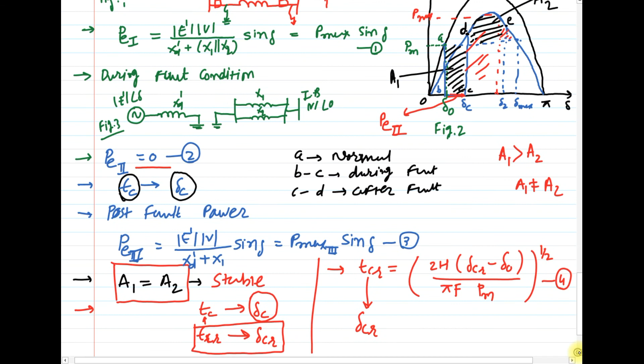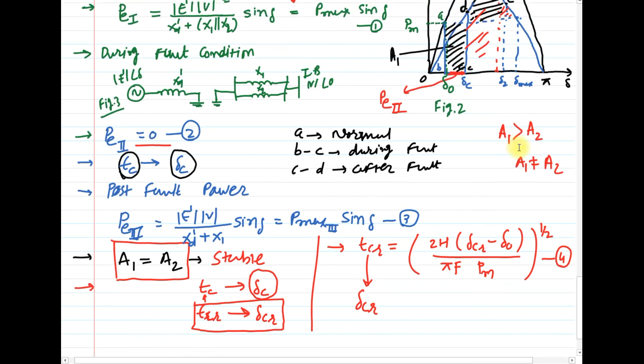We know very well that angle delta C, that means the clearing angle, totally depends on the clearing time, which is TC. So according to the fault clearing time, we get delta C. The general conclusion of the theory is that we need to clear the fault before delta C. That means we get two different terms: TCR, which is the critical clearing time, and with respect to that we get an angle, which is delta CR, that means the critical clearing angle. Clear? I hope you are clear up to this. And if you have any doubt, you can ask or even mail me. Okay.